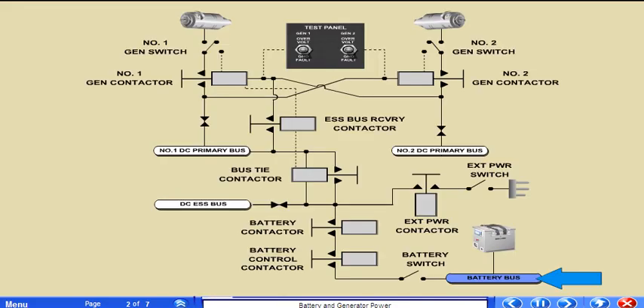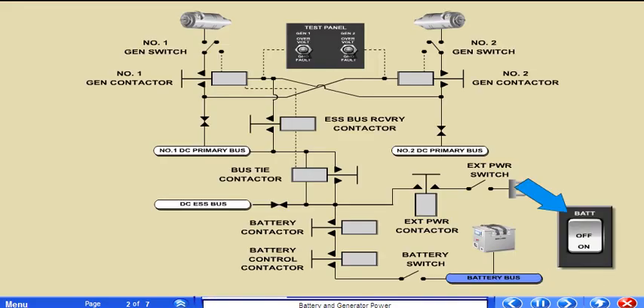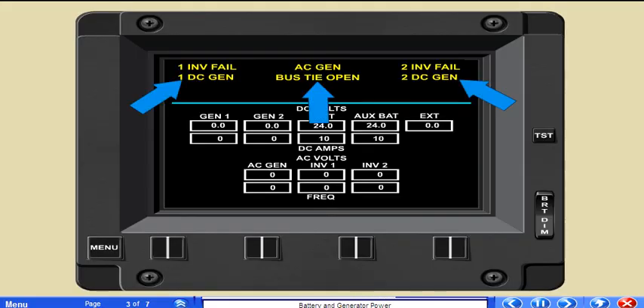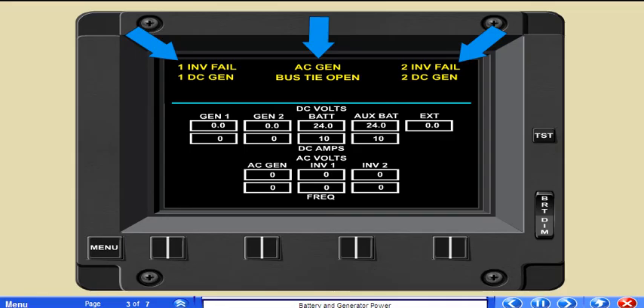The battery bus is powered continuously, regardless of the position of the battery switch, so long as the charged battery is physically connected to the bus bar. Placing the battery switch to on causes the DC essential bus to be powered via the battery contactor. When the battery switch is moved to on, the battery contactor closes automatically and battery power energizes the DC essential bus. Note that both generator caution messages and the bus tie open message are now illuminated. Also, if equipped, the AC generator and the number 1 and number 2 inverter fail messages illuminate.